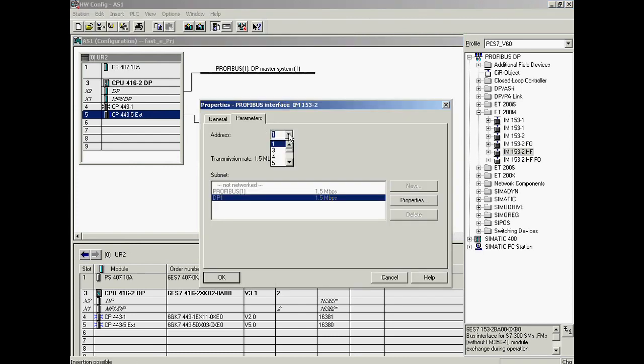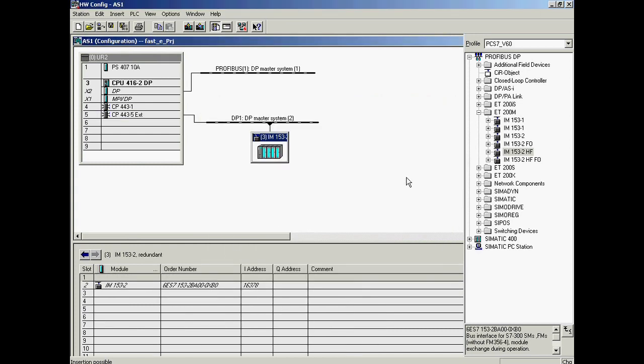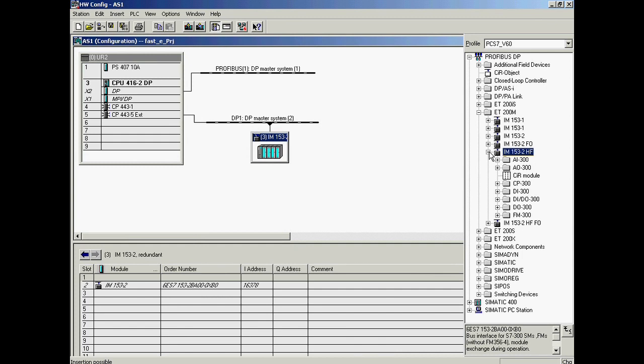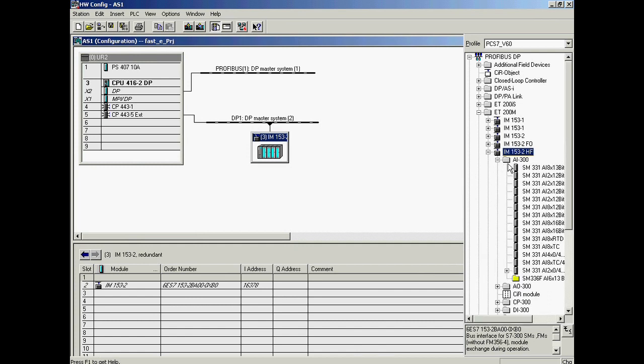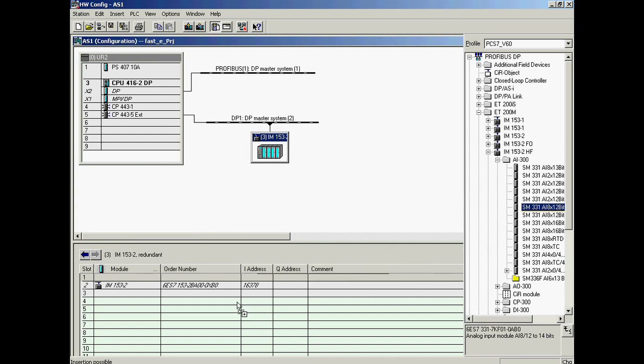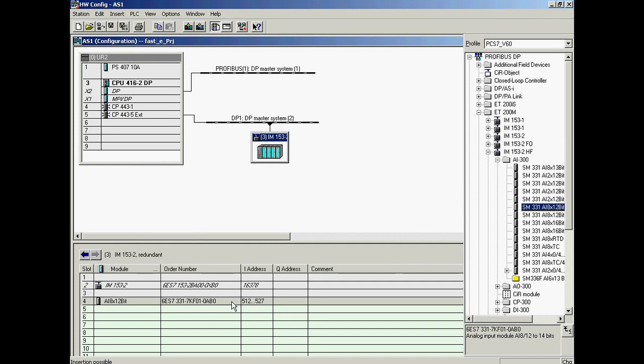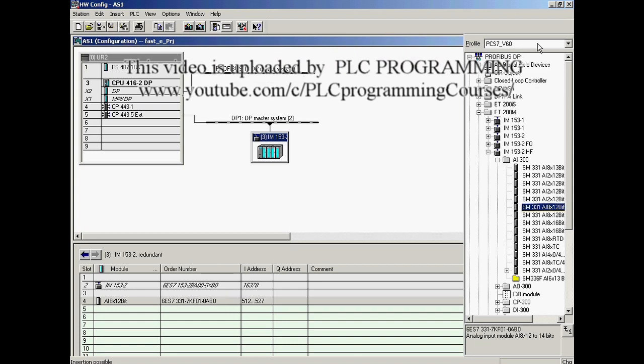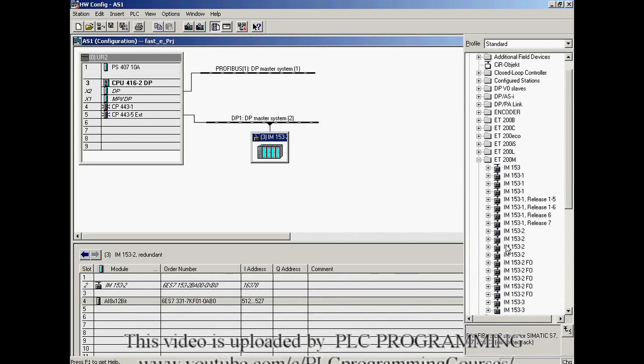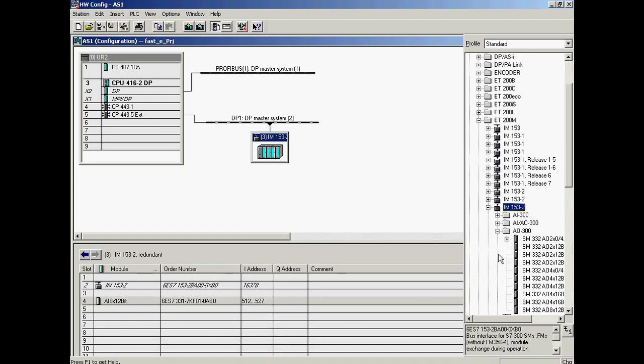The address is set to 3. The ET200M is equipped with an analog input, an analog output, a digital input, and a digital output, all of which will be configured. The analog input module is plugged into slot 4 — this module is from the PCS7 V6.0 optimized catalog. The analog output module is plugged into slot 5, from the standard hardware catalog which contains all modules supported by SIMATIC PCS7.